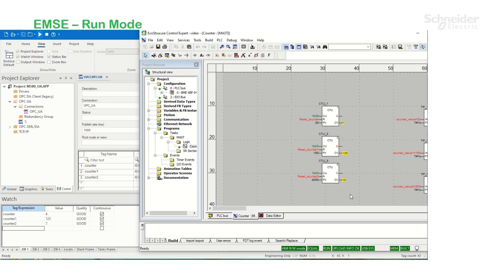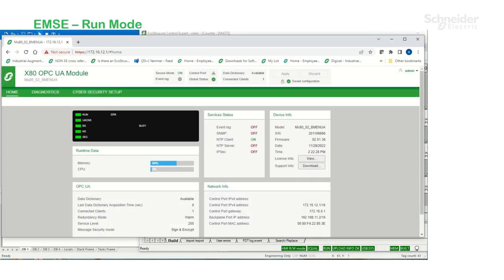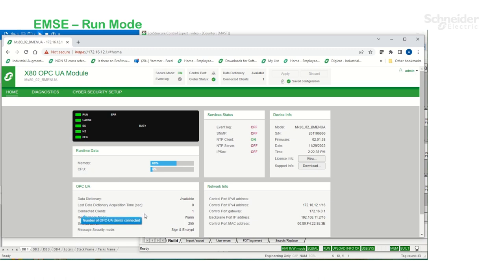And lastly, if you want to take a look at the webpage of the BME NUA module, you can see that all the LEDs are steady green, indicating that I have connectivity with an OPC UA client. This concludes the video.